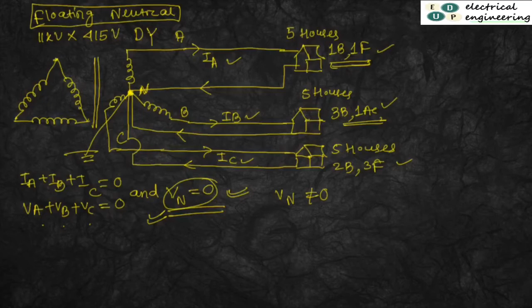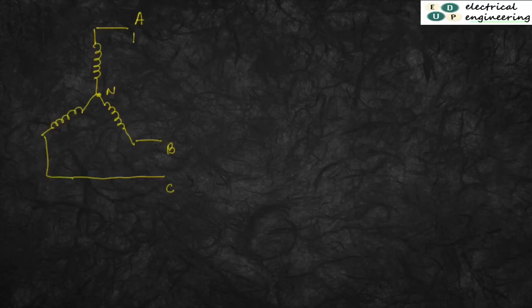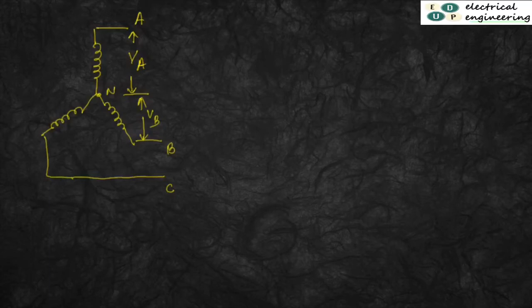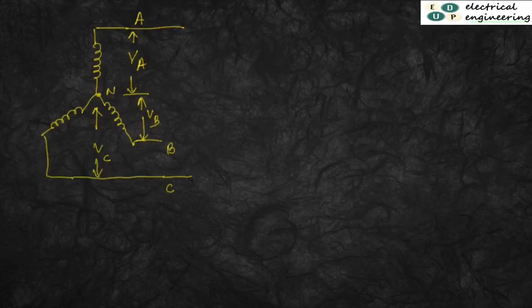Now let's discuss how the phase voltage becomes equal to the line voltage when a fault occurs in any of the 3 phases. Suppose this is your secondary winding, star connected, and this is A, this is B, and this is C. This is the neutral, and the voltage appearing across A and N is the A phase voltage. Similarly this is the B phase voltage, and this is the C phase voltage. Now suppose a fault occurs at point B, means the B winding gets short circuited. Now this total winding is bypassed, so the neutral is no longer balanced. Initially our voltage would be the line voltage VAB.